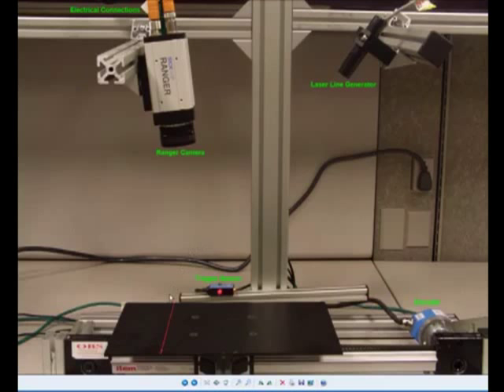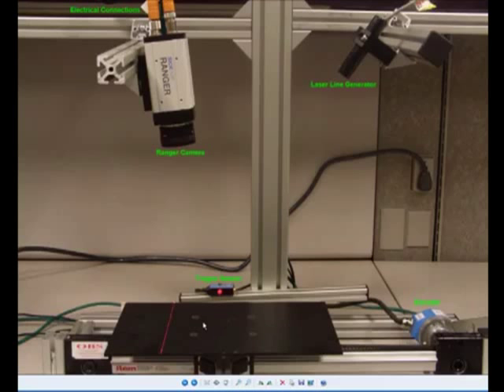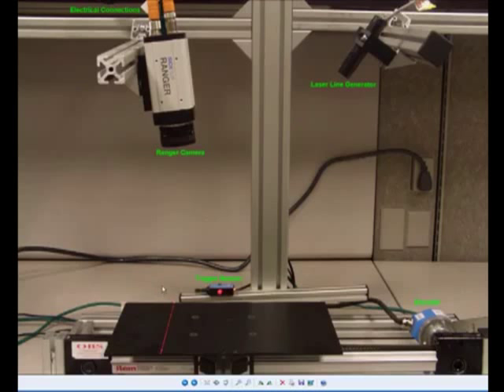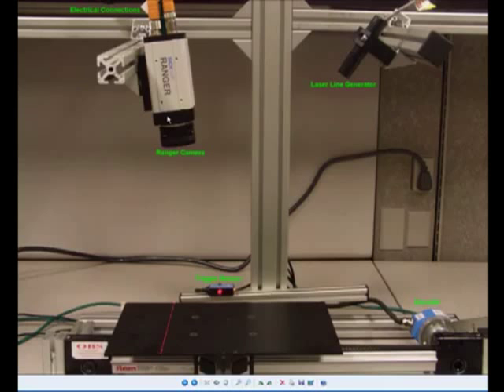The laser obviously is there because the camera looks at the displacement of the laser and acquires profile by profile. And I have the slider over here to execute the movement so that when I move my object from left to right or vice versa, different portions of the object are coming in front of the camera with the laser on top of it. So the camera is able to acquire profile by profile. And then all that is combined to create a three dimensional image.